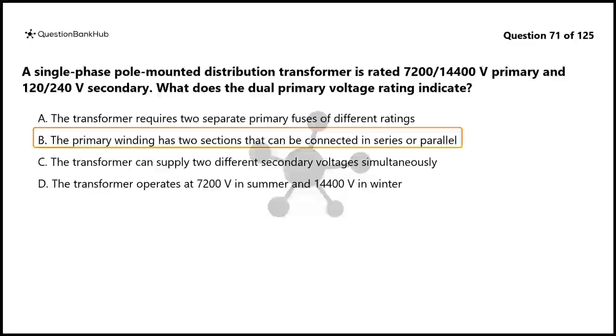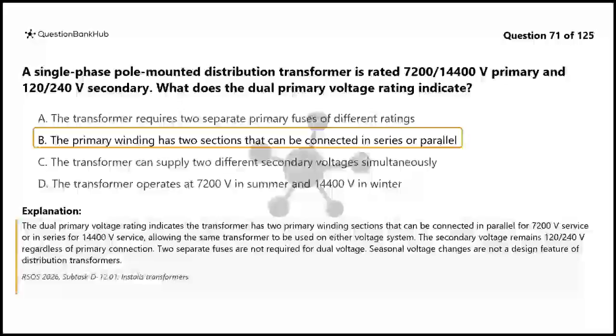The correct answer is B. The dual primary voltage rating indicates the transformer has two primary winding sections that can be connected in parallel for 7,200 V service or in series for 14,400 V service, allowing the same transformer to be used on either voltage system. The secondary voltage remains 120 over 240 V regardless of primary connection.